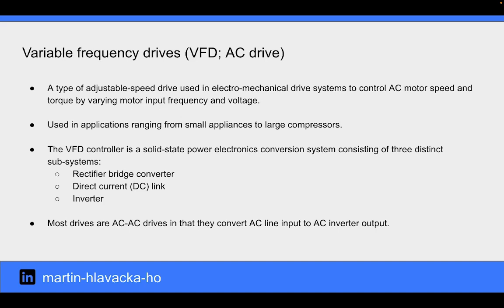A variable frequency drive is a type of adjustable speed drive used in electromechanical drive systems to control AC motor speed and torque by varying motor input frequency and voltage. VFDs are used in applications ranging from small appliances to large compressors. The VFD controller is a solid-state power electronics conversion system consisting of three distinct subsystems: a rectifier bridge converter, a direct current link, and an inverter. Most drives are AC-AC drives in that they convert AC line input to AC inverter output.